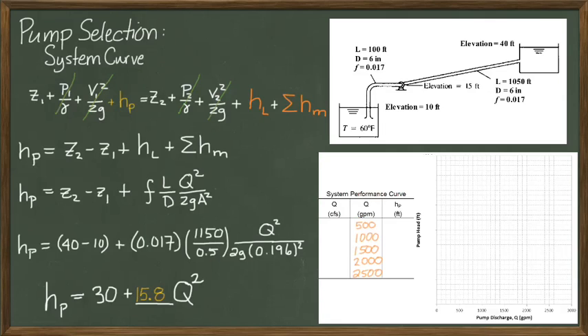Darcy-Weisbach equation uses Q in cubic feet per second, so we take our gallons per minute and insert in all the CFS values. And now that we have the CFS values, we can use our system curve equation to tell us what is the corresponding head that needs to be overcome in the system.